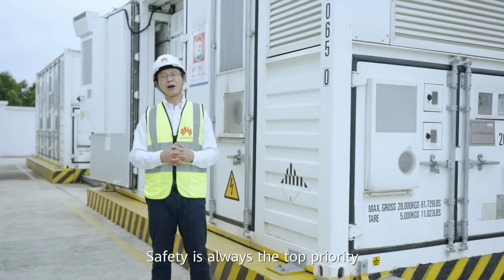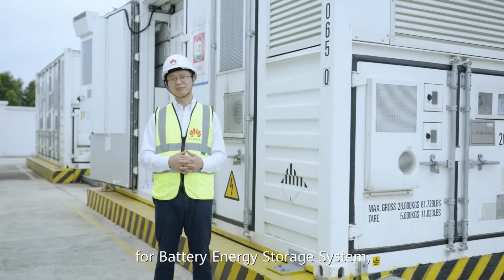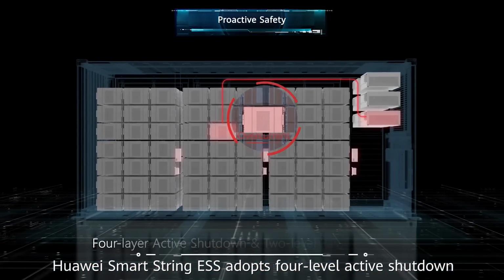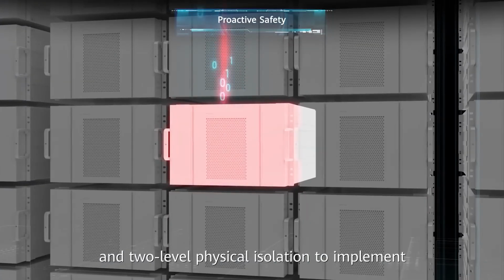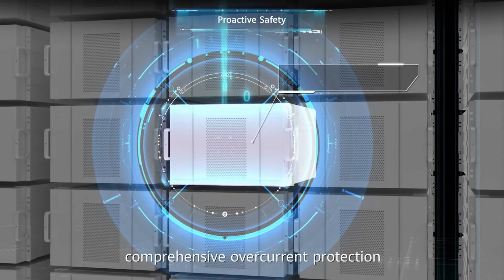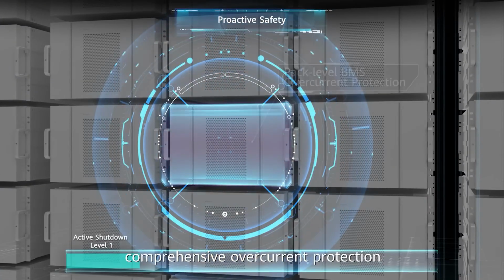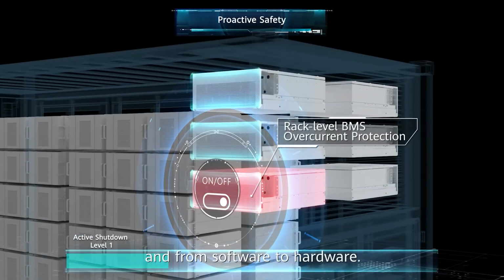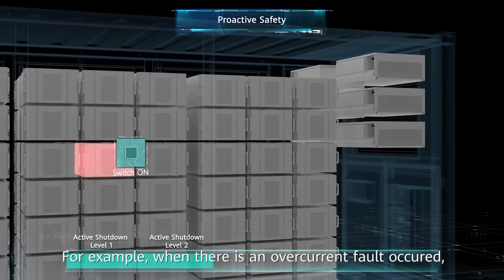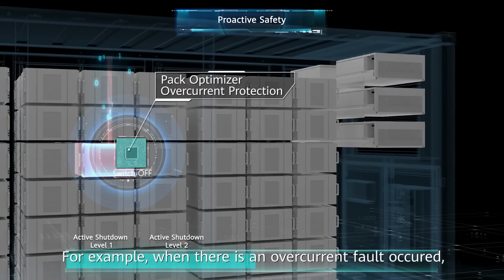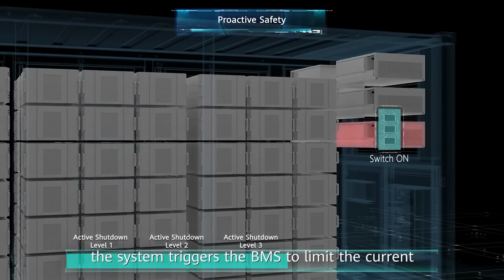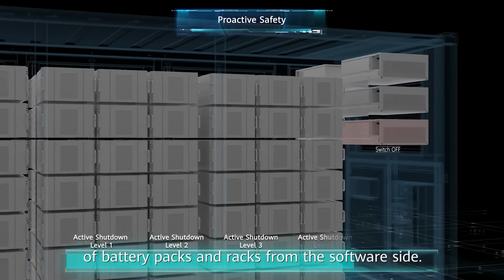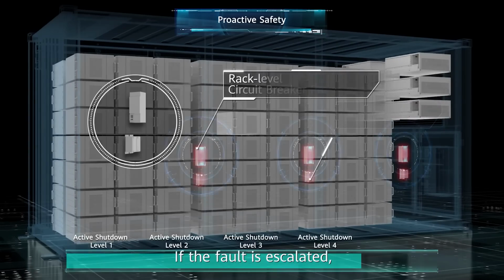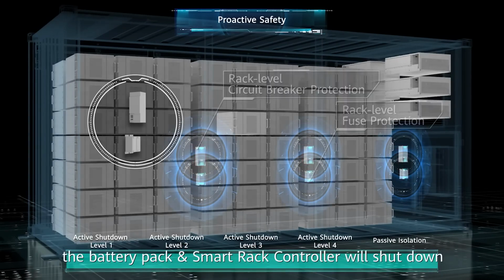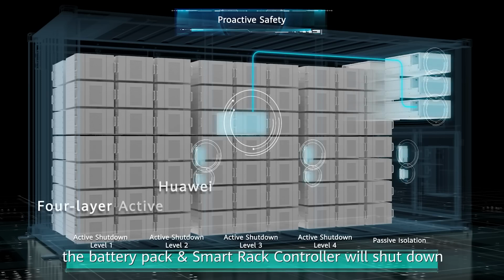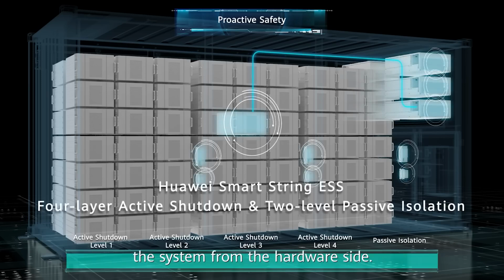Safety is always the top priority for battery energy storage system. HUAWEI Smart String ESS adopts 4-level active shutdown and 2-level physical isolation to implement comprehensive overcurrent protection from battery packs to system and from software to hardware. For example, when an overcurrent fault occurs, the system triggers the BMS to limit the current of the battery packs and racks from the software side. If the fault is escalated, the battery pack and the smart rack controller will shut down the system from the hardware side.